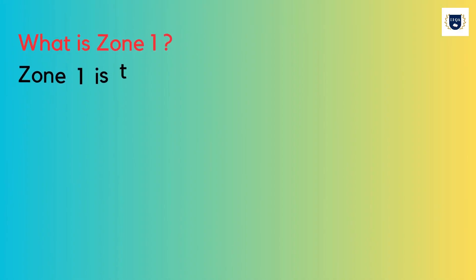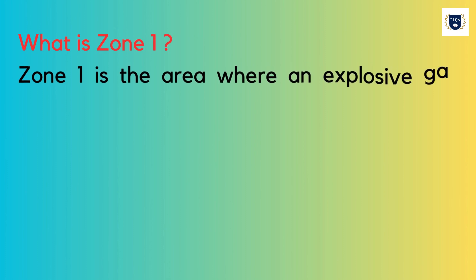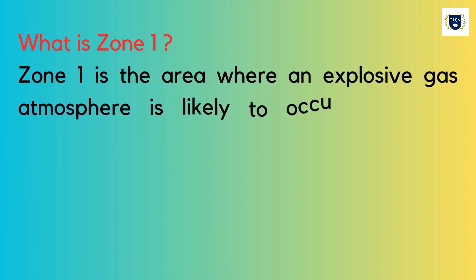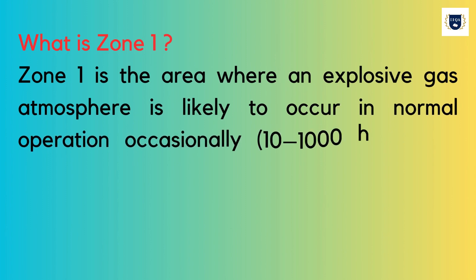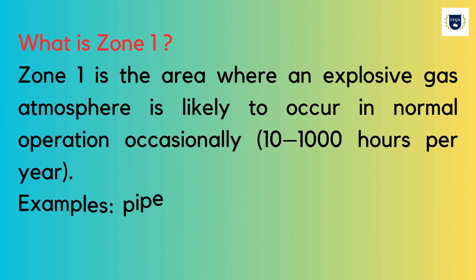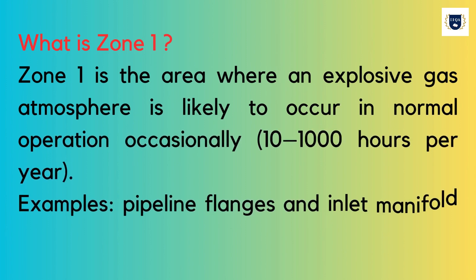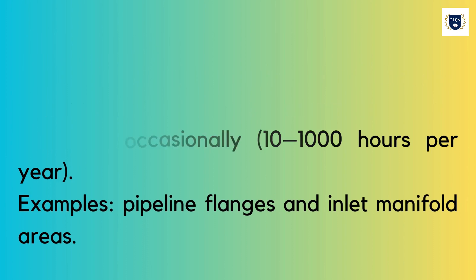What is Zone 1? Zone 1 is the area where an explosive gas atmosphere is likely to occur in normal operation occasionally, between 10 to 1000 hours per year. Examples include pipeline flanges and inlet manifold areas.